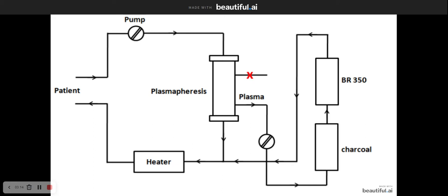The plasma is retained while cells are returned to the patient and re-infused. The patient's blood is let through the hollow fiber capillaries of a plasmapheresis filter. The filter uses a permeable membrane to separate according to size the smallest components, plasma, from the large components, which are cells.